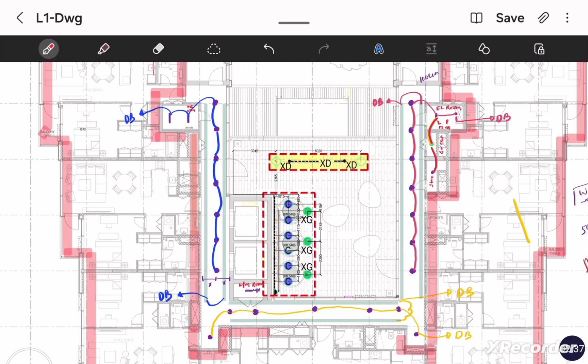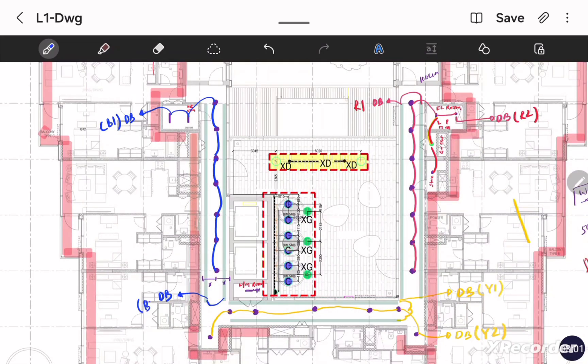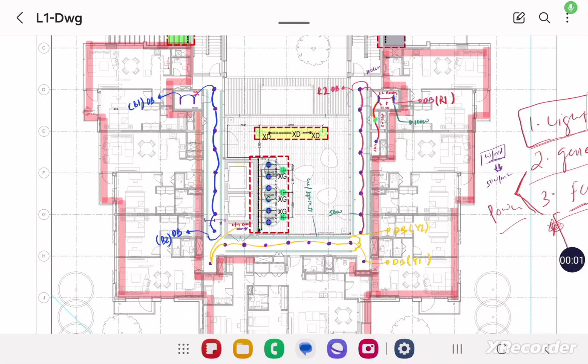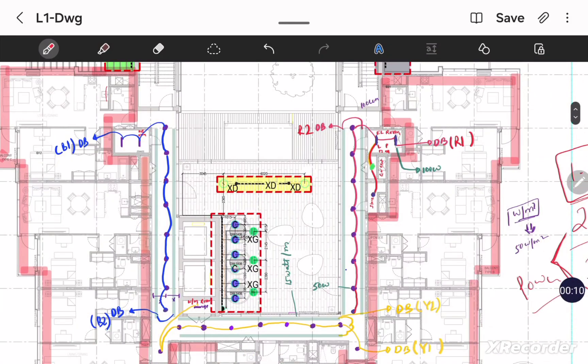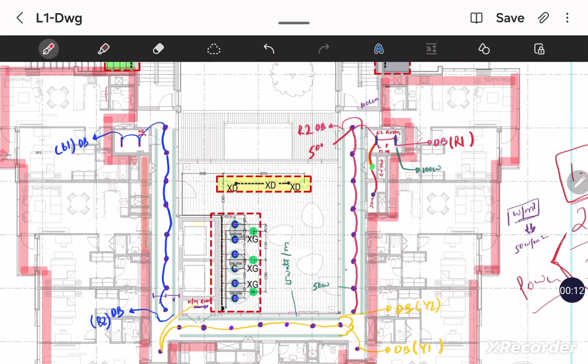We will also add circuit markings: R1 and R2 for the red circuits, Y1 and Y2 for yellow, B1 and B2 for blue — making it a very small DB. Now we will make the load schedule for the first floor common area light DB. After referring the material submittal, the corridor light is 50 watt, the tube light is 100 watt, and the strip light is 15 watt per meter.